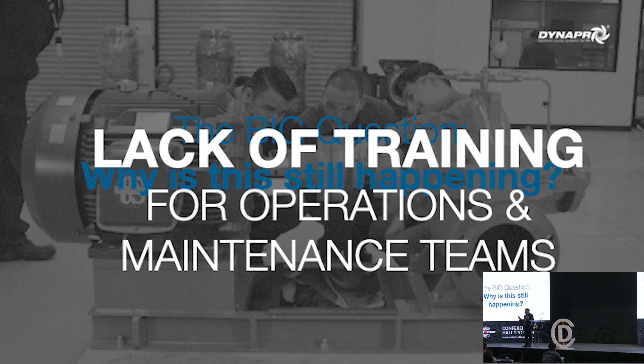The big question is: why is this still happening? The reason is lack of training. When I searched for training available in the market for maintenance and operations teams, it was basically pump companies training them to assemble and disassemble their pump and handing them a book on how to start it, shut it down, and which parts to order for operational problems. The real problem is in the operation of the system — identifying things like air in the system, tank sizes, everything engineering firms consider during selection — and the maintenance and operations teams don't have that knowledge.